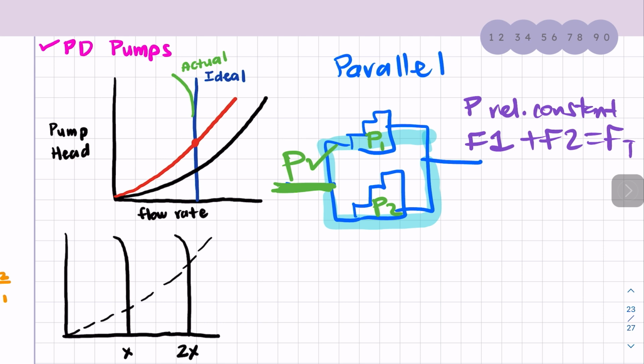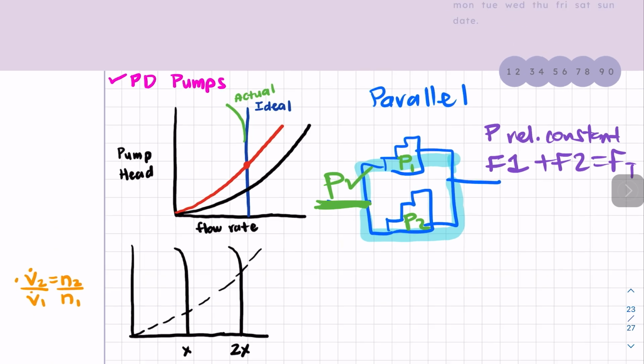However, it's very important to note that in parallel operation, the pumps must be carefully sized and selected to ensure they operate within their design parameters. If the pumps are too small or too large, they might not operate efficiently, or you could have issues with pump cavitation or other problems. That's why proper sizing, selection, and installation are so important, specifically for PDPs in parallel—it helps ensure maximum efficiency of the pump in your system if everything is picked properly.